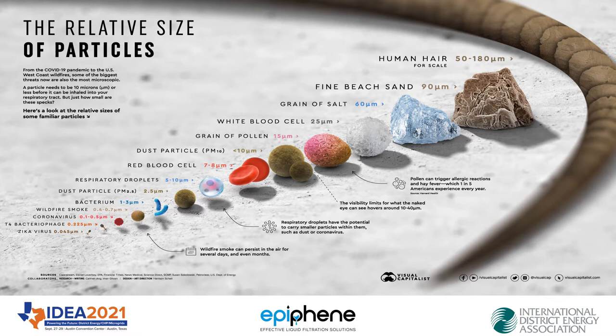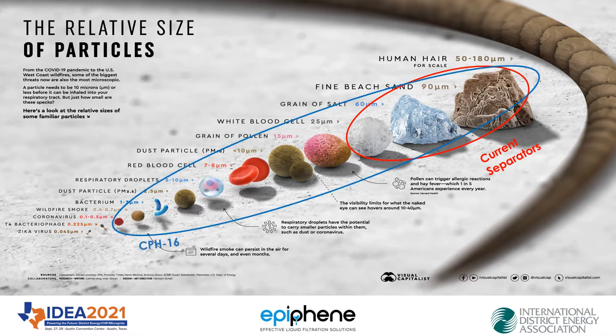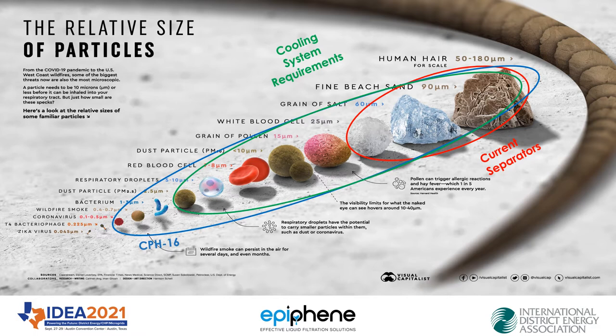The size of these particles — human hair is typically about 50 to 60 microns. In this situation, we see beach sand at 90, and usually at 74 to 90. Silt starts at anything below 74 micron. You can see here we've got salt, we've got a white blood cell. If you look at what current separators can do — very small separators like 2 or 3 inch inlet might get some 25 micron. Then you look at that compared to where we're operating: not only can we get the larger particles where the current separators do okay, we can get all the way down to a half micron. For cooling towers, if we can get to 5 micron and above, we've done a very, very good job. The range of what the separator is able to do far and away exceeds the expectations.